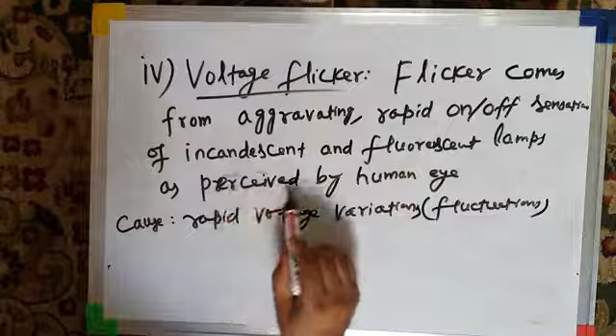Whenever voltage rapidly changes, the light of your incandescent lamp also changes, because the light intensity of your incandescent lamp or fluorescent lamp is highly sensitive to voltage variations. So whenever there are rapid voltage variations, the light output of the lamp also rapidly changes. It gives rise to an aggravating rapid on-off sensation as perceived by human eye. So this is called flicker. This is where flicker comes from.